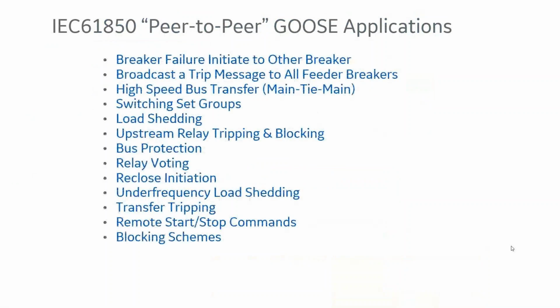And some of the applications that we can apply this to is breaker failure. When I need to initiate breaker failure, or if I need to broadcast tripping, like if I have a bus differential trip, I need to trip multiple breakers. I can broadcast that message to multiple breakers to be able to trip them without having to wire anything into those trip circuits. Main-tie-main transfer schemes, instead of doing the wiring, I could do it over communication, load shedding, zone interlocking, relay voting, reclose initiation, frequency load shedding, transfer tripping, and all sorts of applications, not limited to the ones I have up here. These are the most common ones.